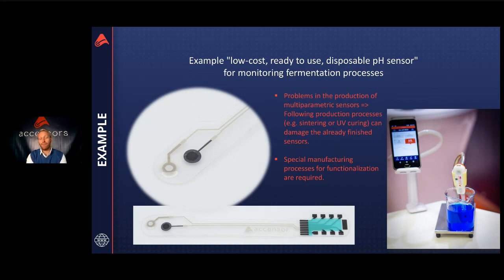But if you have finished the reference electrode before, and you go with this finished reference electrode, because it's on the same stripe, into the last process for the finished pH electrode under UV light, you will damage the reference electrode. And this means you have requirements for how to manufacture a sensor system from different elements.